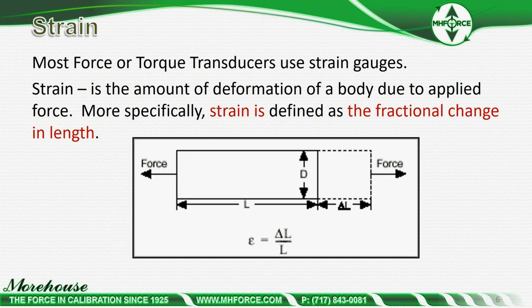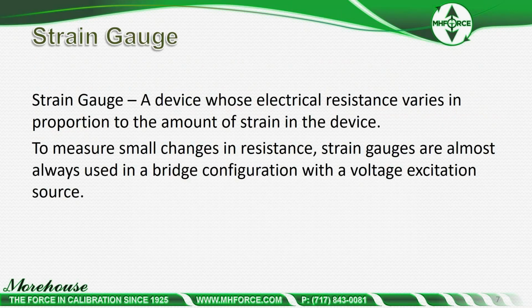First, let's talk about what's in a load cell. Typically, there's strain gauges in a load cell, and strain gauges are used to measure strain. Most force or torque transducers use strain gauges. Strain is the amount of deformation of a body due to applied force. More specifically, strain is defined as a fractional change in length. A strain gauge is a device whose electrical resistance varies in proportion to the amount of strain in the device.